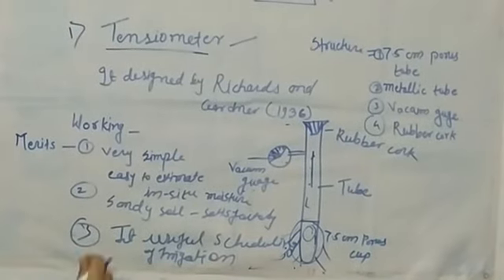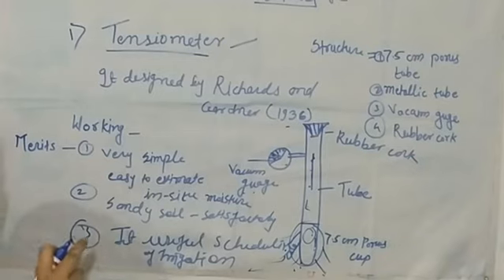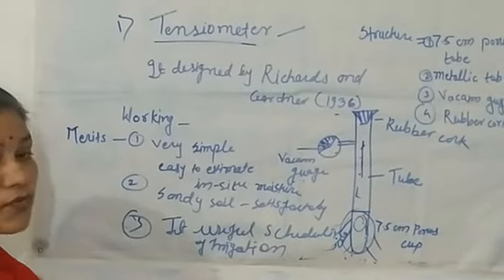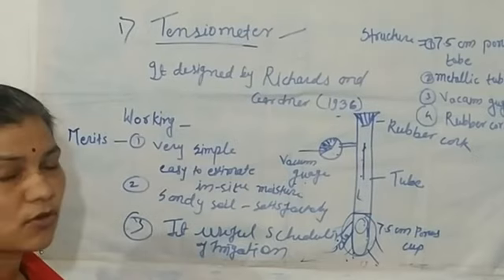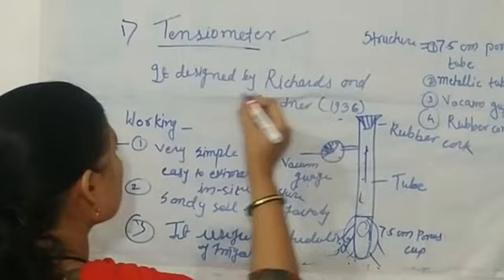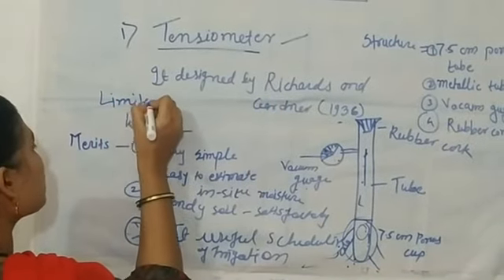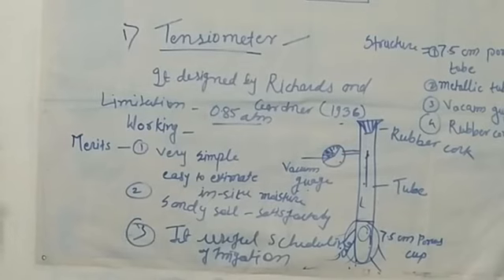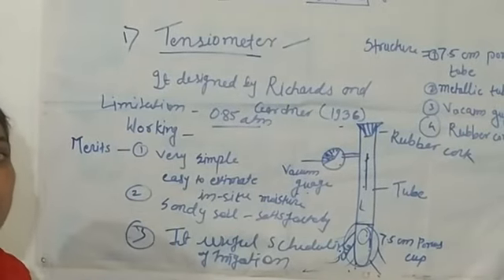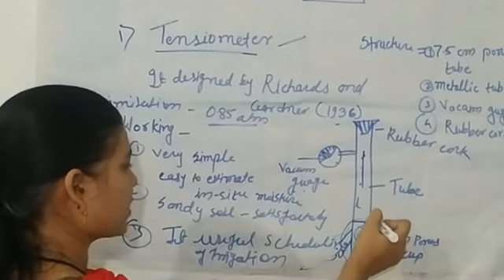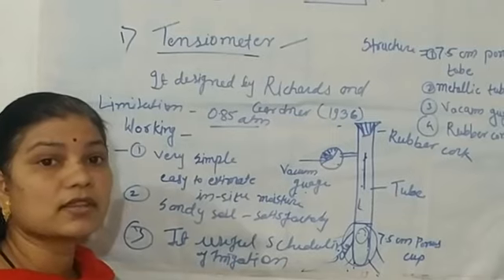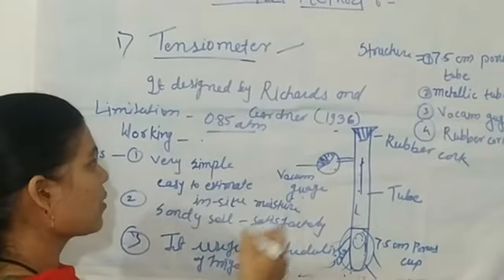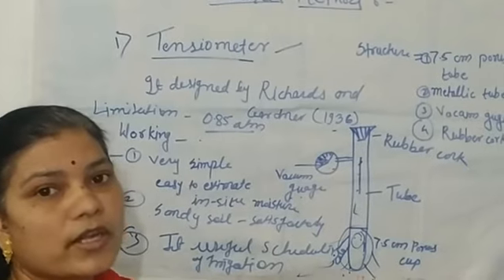The limitations of the tensiometer: it works satisfactorily only up to 0.85 atmospheric tension. When the tension increases beyond 0.85 atmospheres, air enters the vacuum gauge and the system no longer gives accurate readings for a longer period.